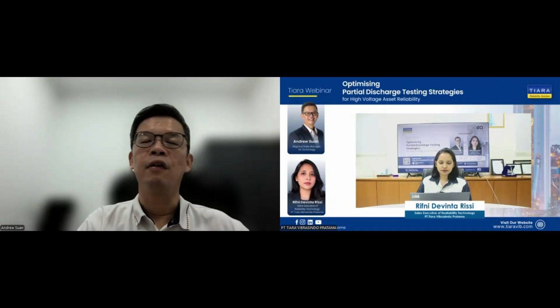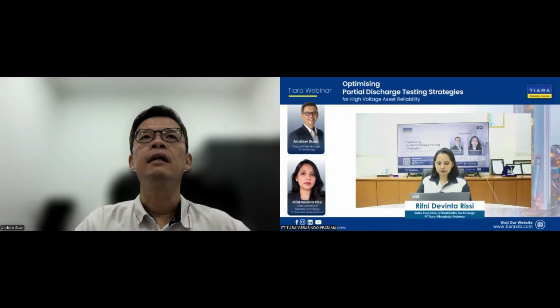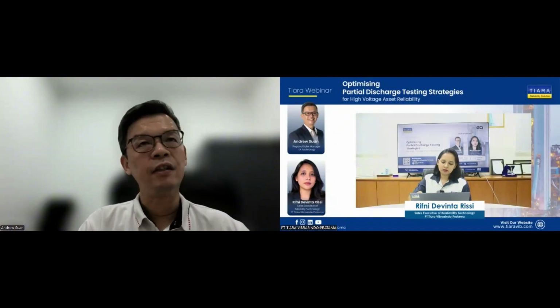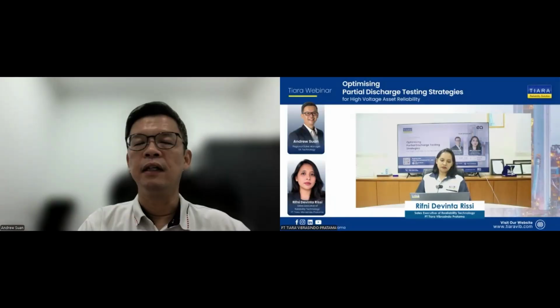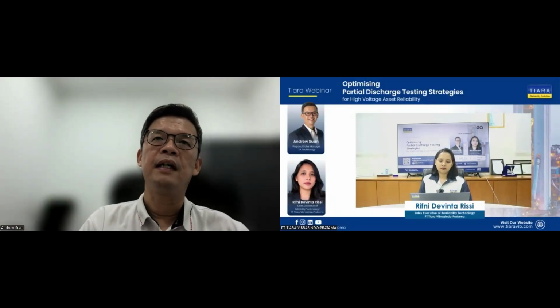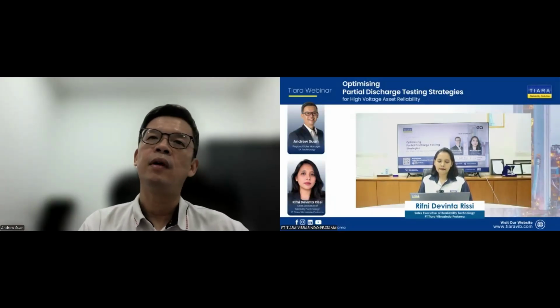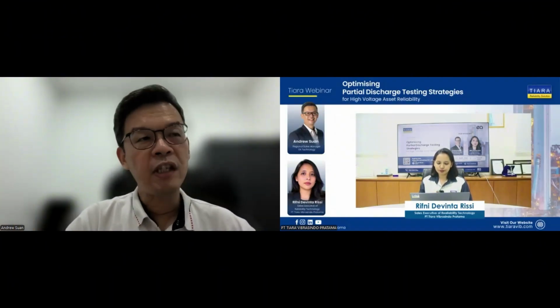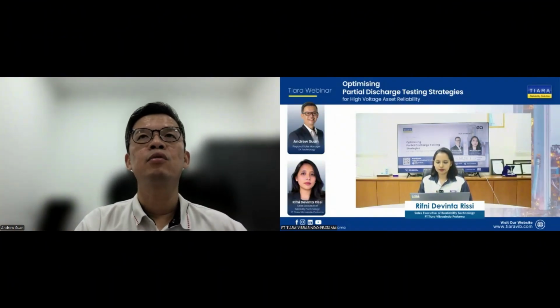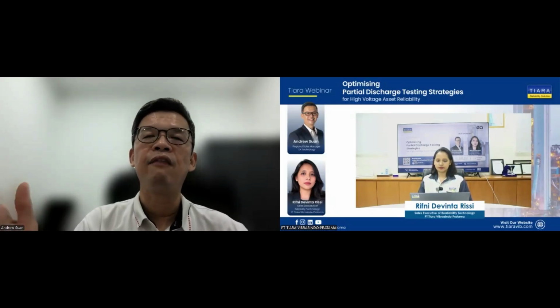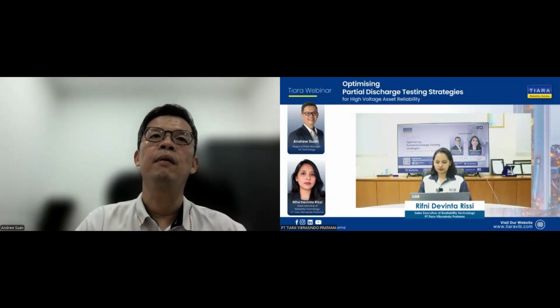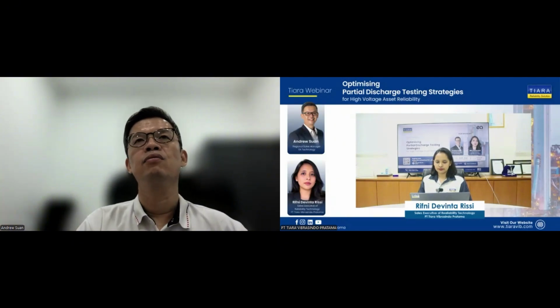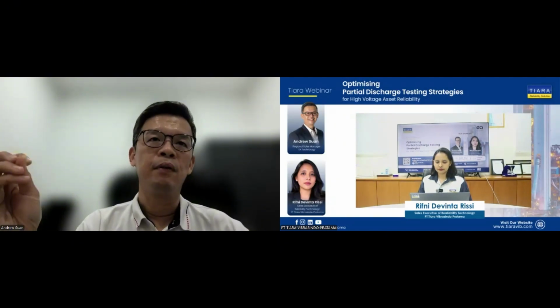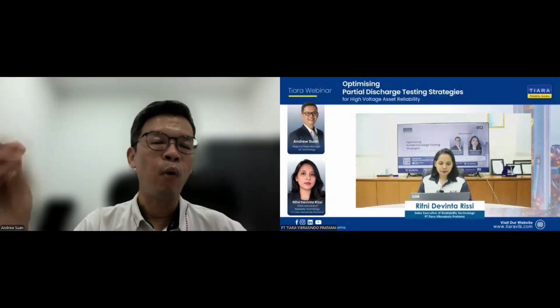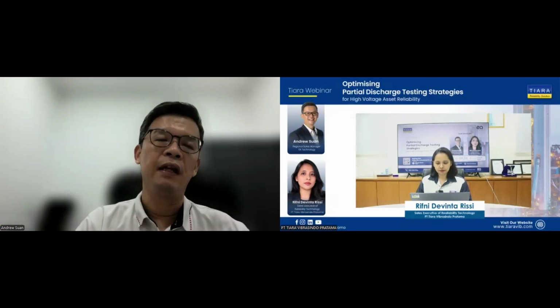Online with permanent monitoring actually lets you detect the problem faster, giving you an alarm in the shortest possible time so you have more time to plan. So for businesses and utilities, going online definitely helps solve a lot of problems. Offline is for you if you want to verify the problem, confirm there's really a PD and where it is - then offline is a very good test.